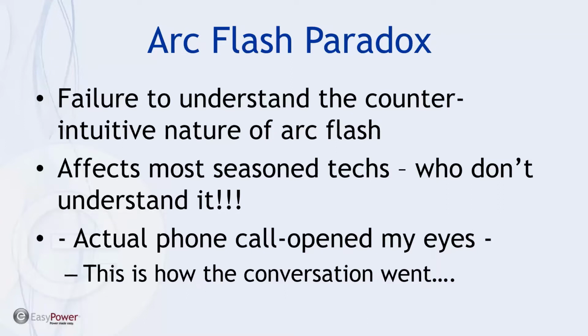He said, put a plain bus on the secondary side of the transformer. And again, it wants to know the voltage that's coming out of the transformer. Everything's in kilovolts, so I type in 0.48. He said, extend this bus about half the width of the screen and drop a cable on each side. So the cable is a circle with 3 inscribed circles. Click it once, put the crosshairs on the bus, click a second time, do the same thing on the other side. He said, terminate each cable with a plain bus.